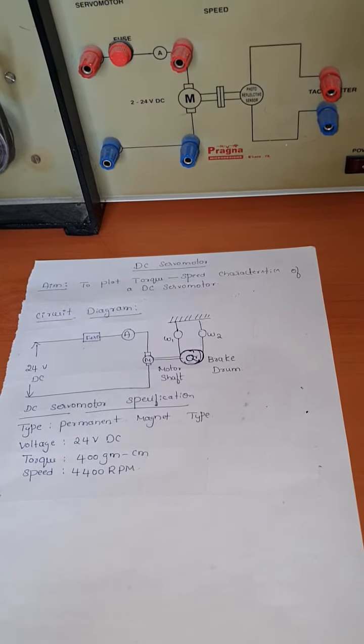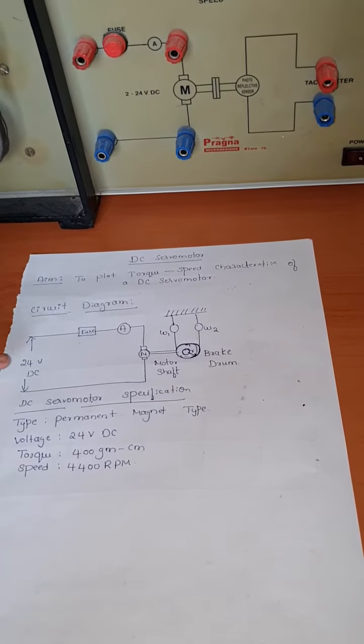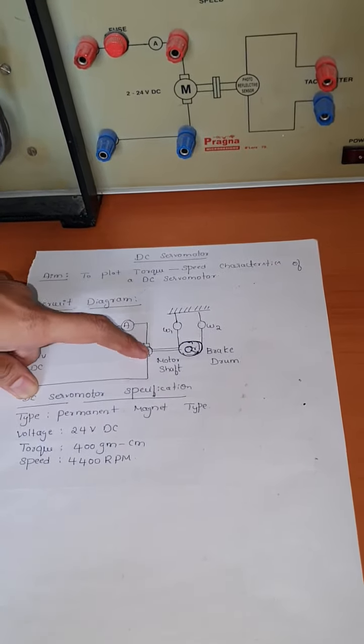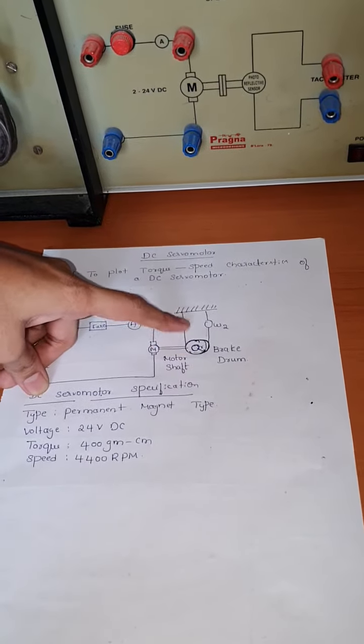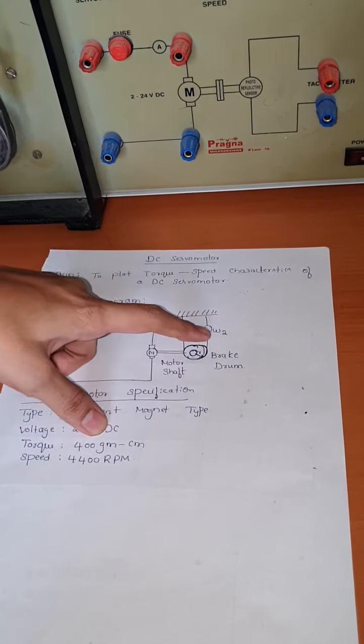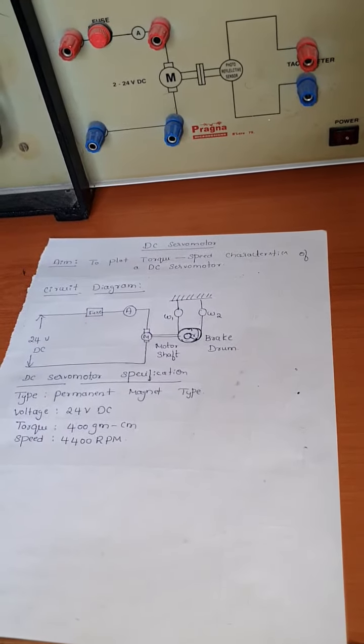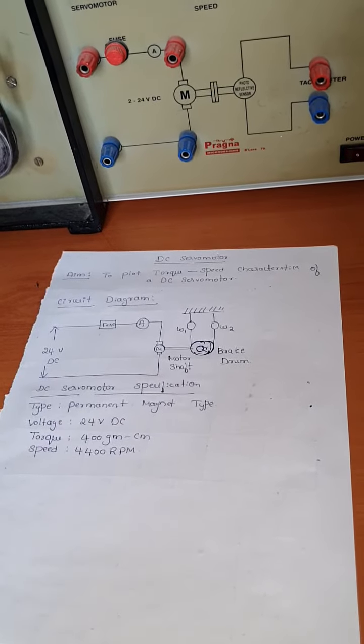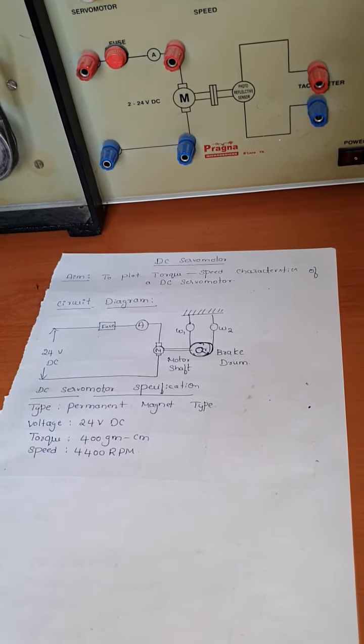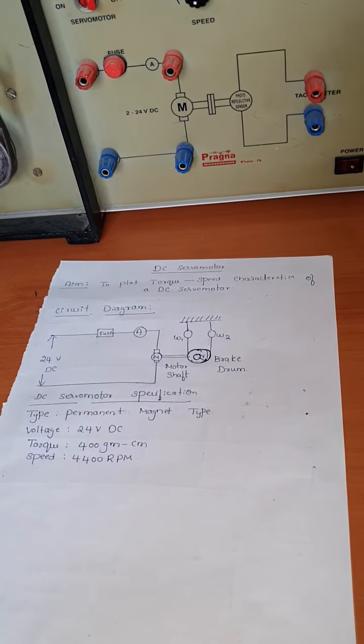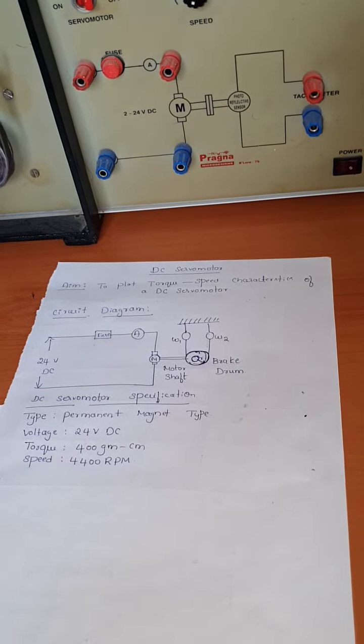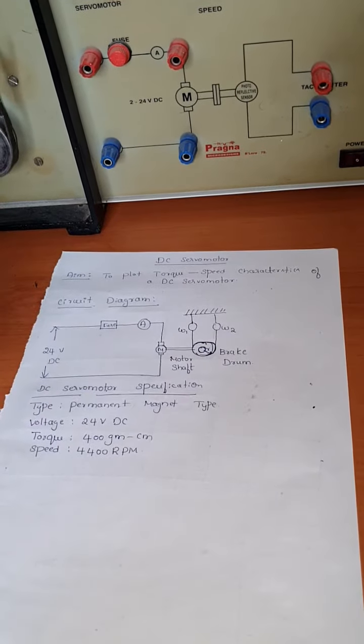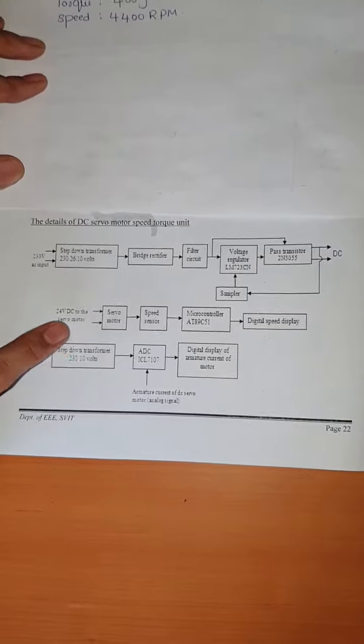Coming to the circuit diagram for the DC servomotor: the input supply is 24V DC, fed to the fuse, then an ammeter, and then the DC motor. The DC motor is coupled to the load, which here is a brake drum providing variable load. W1 and W2 are the two load weights. As load increases, torque and speed are affected. The input voltage is 24V DC, and the rated speed of the servomotor is 4400 RPM.